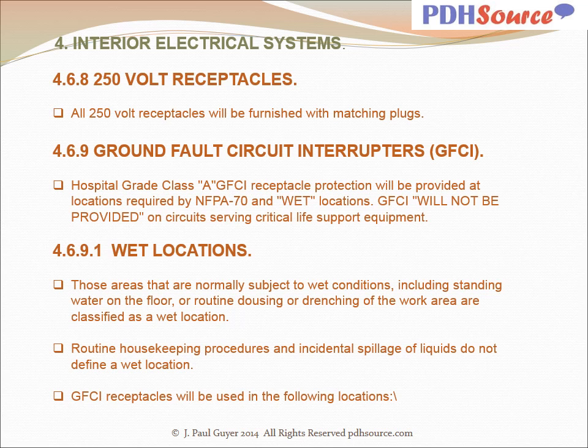All 250 volt receptacles will be furnished with matching plugs. Hospital grade class A GFCI receptacle protection will be provided at locations required by NFPA 70 and wet locations. GFCI will not be provided on circuits serving critical life support equipment. Those areas that are normally subject to wet conditions, including standing water on the floor or routine dousing or drenching of the work area, are classified as a wet location. Routine housekeeping procedures and incidental spillage of liquids do not define a wet location.